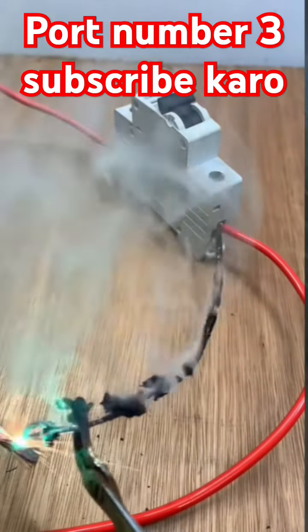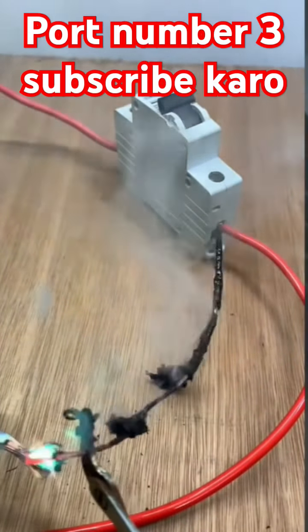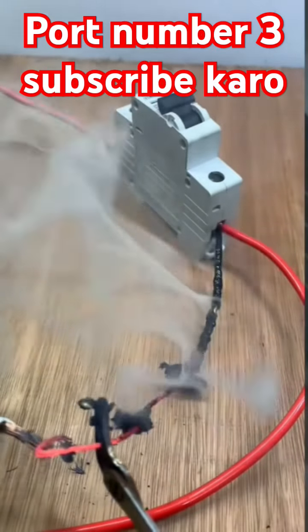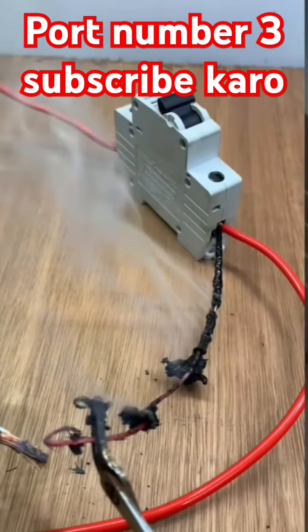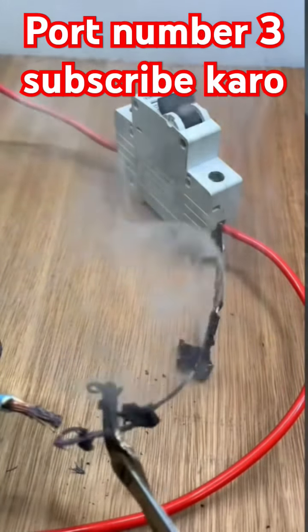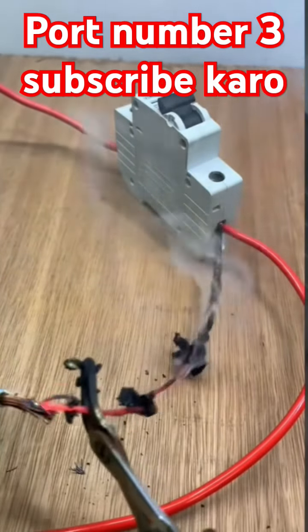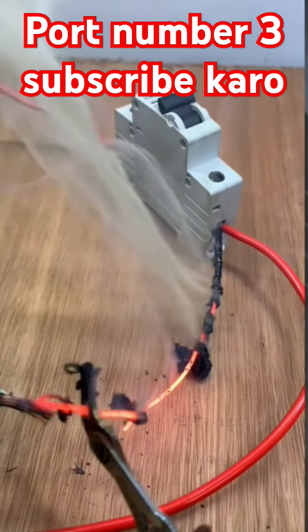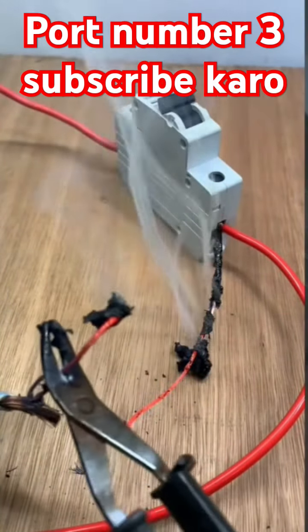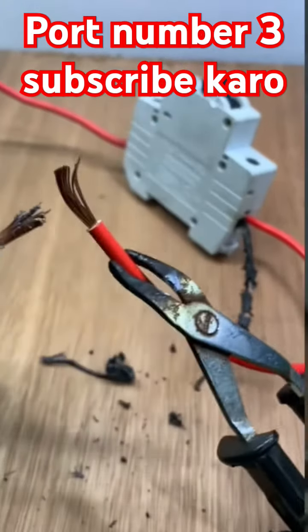What happens if you fold the cable in half? The circuit breaker still won't trip. Look, the cable catches fire, and it could catch fire in your installation. The cable is close here, but you could have an outlet far away on this same circuit, just because you connected it to this circuit breaker here, look.